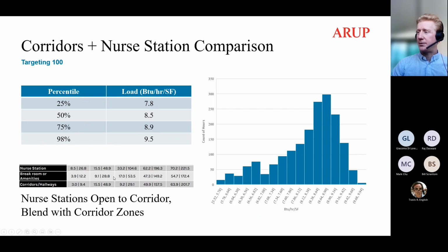It tends to align closer to where we would expect nurses stations, which are a smaller percentage of that total zone area, and a blend of corridors to potentially be. So this likely merits further investigation, but I think it is an interesting point that there can be places where perhaps a combination of those zones, particularly when there is a flowing volume or where there's similarity and they can be blended across areas, may be appropriate as an energy modeling approximation that still replicates the reality.